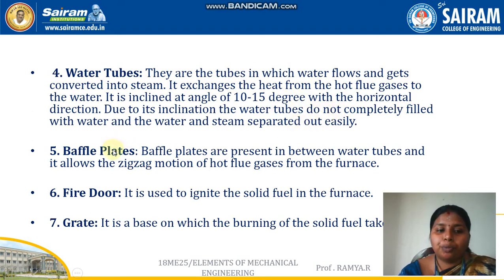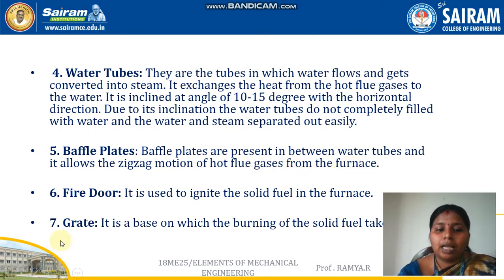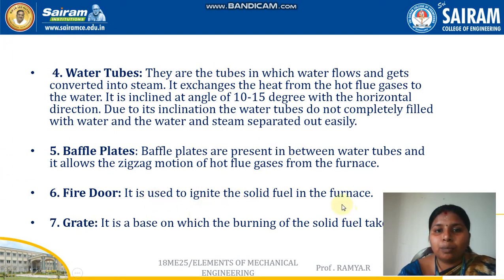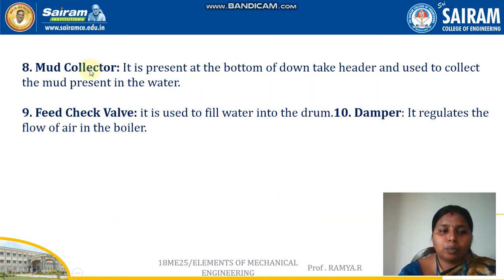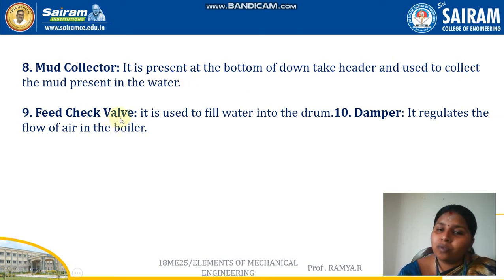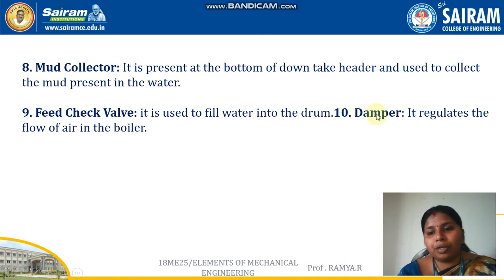Baffle plates are kept between the water tubes and allow a zigzag motion of hot flue gases from the furnace. The fire door is used to ignite the solid fuel. The grate is the base on which burning of solid fuel takes place. The mud collector is present at the bottom of the header and collects mud present in the water. The feed check valve is used to fill water into the drum, and the damper regulates the flow of air in the boiler.